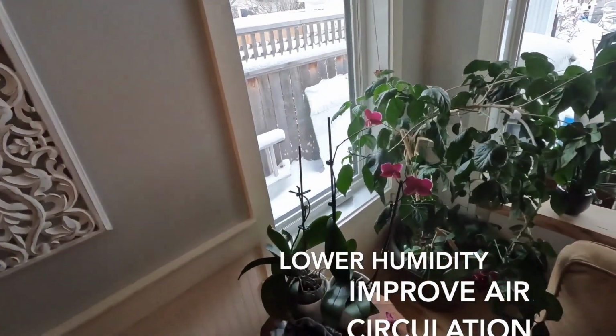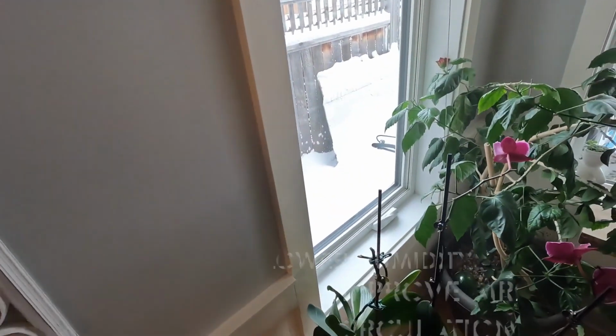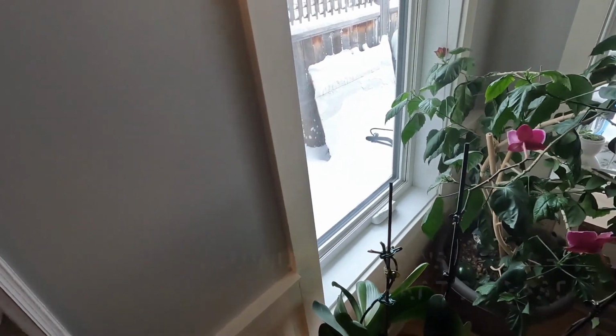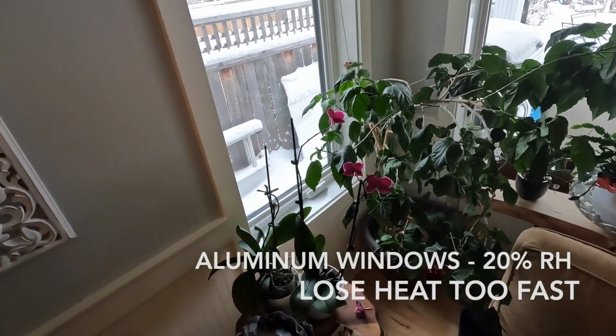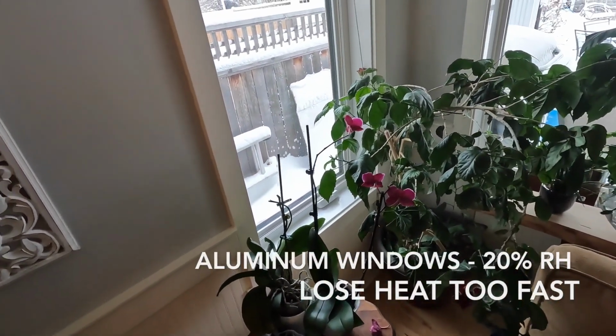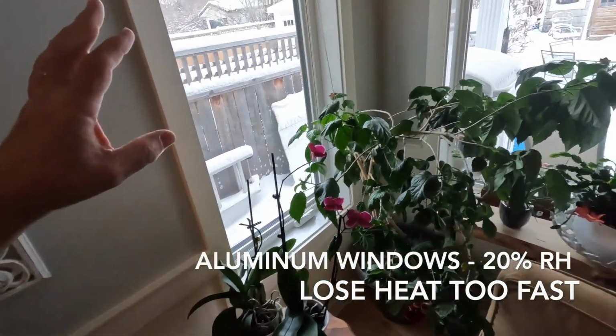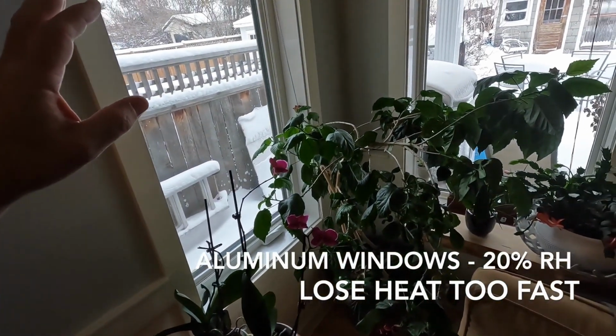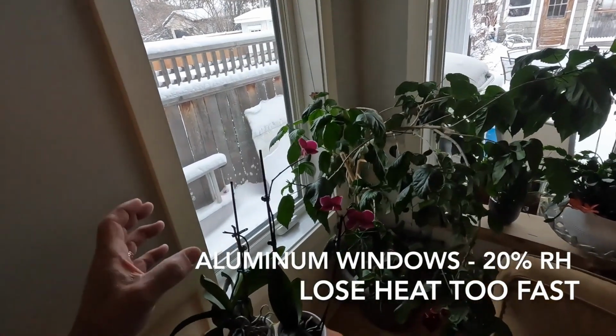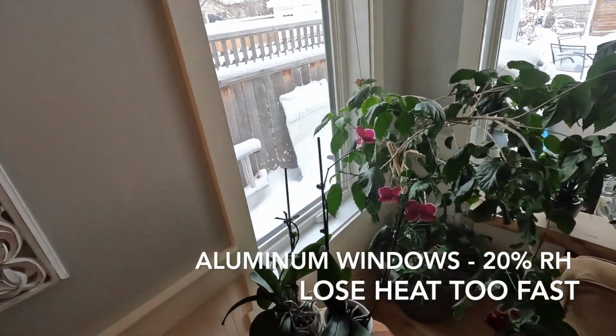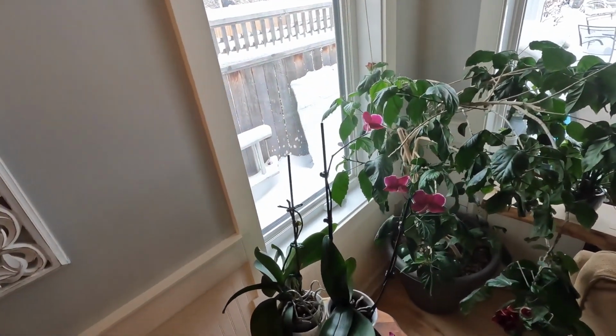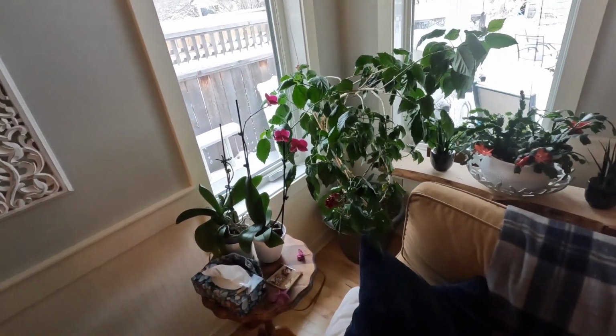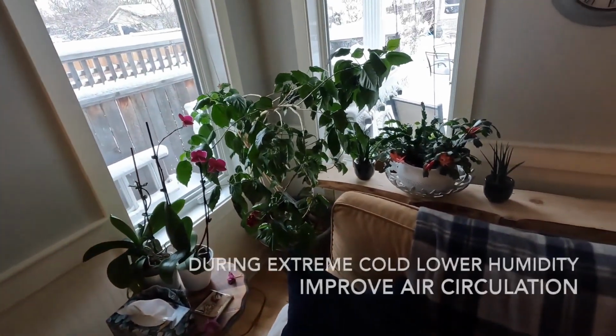Here's another point too. If these are metal windows, aluminum frame windows, you're going to have to keep your humidity way down. You're going to have to keep that humidity down at around 20% on a day like today at minus 23, because they just can't hold it. There's just not enough there to prevent moisture from forming on those surfaces. So those are some tips on reducing condensation and frost and moisture on the windows.